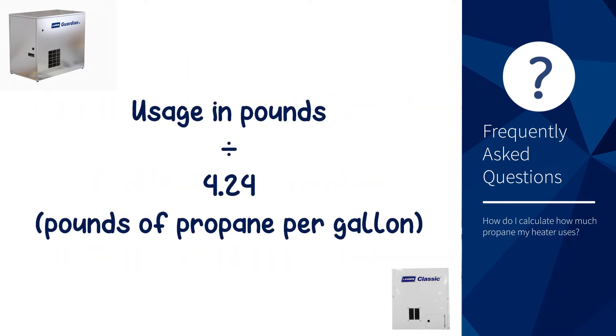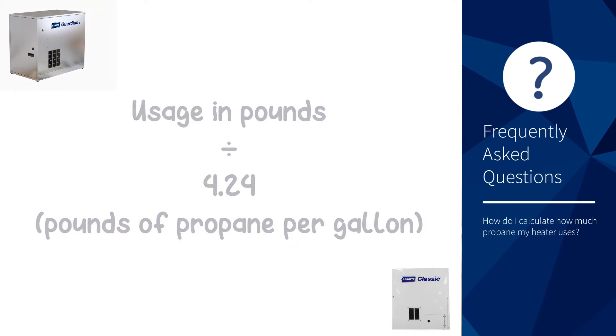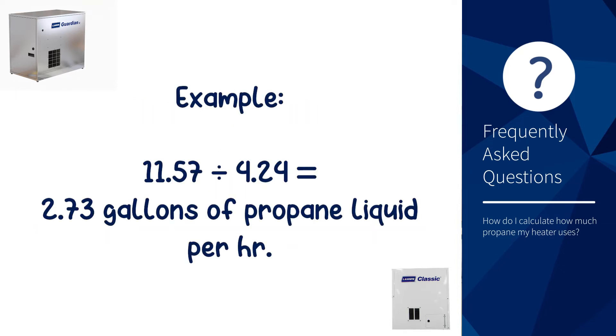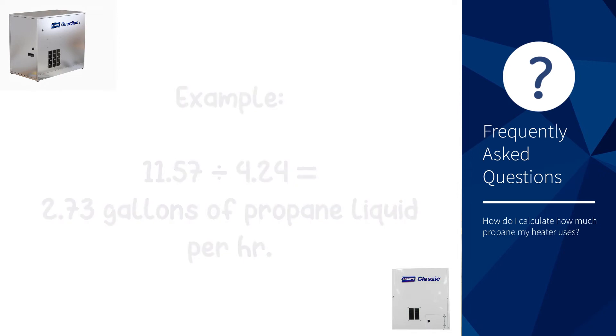To determine gallons of propane used per hour, take usage in pounds and divide by 4.24, which is the pounds of propane per gallon. So for example, the Guardian 250 — we now know it burns 11.57 pounds of gas per hour. Divide that by 4.24 and you get 2.73 gallons of propane liquid per hour.